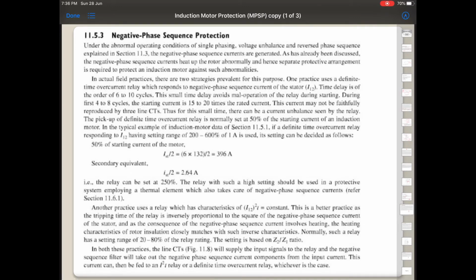One is using a definite time over current relay, which actually responds to the negative phase sequence current of the stator. Now what a definite time over current relay does is, it waits for a certain time and then takes the tripping decision. Why it is required is because during starting the current will be 5 to 6 times the rated current, and due to problems like CT saturation, the CT will not reflect the exact current to the secondary. The core gets saturated, hence the primary current will not be reflected in the secondary, because of which the relay connected in the secondary will not get the correct information, and hence the relay is made to wait for 4 to 8 cycles.